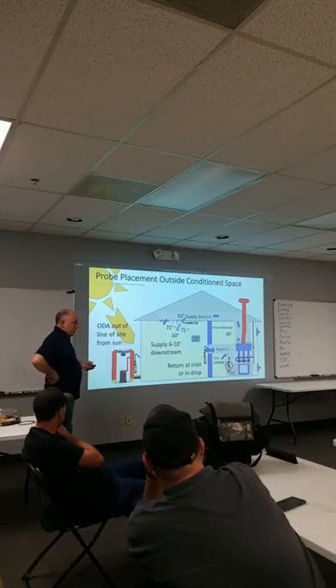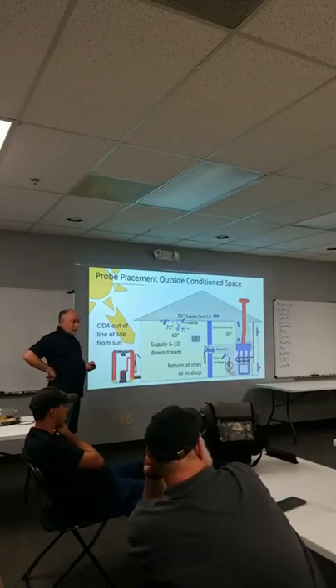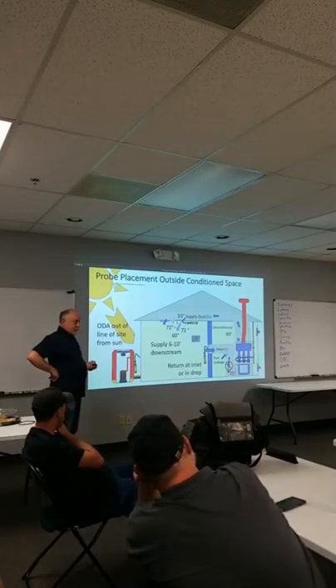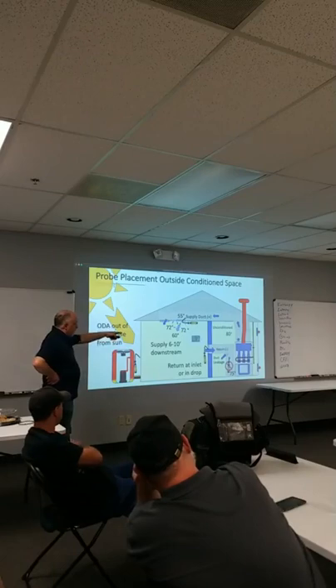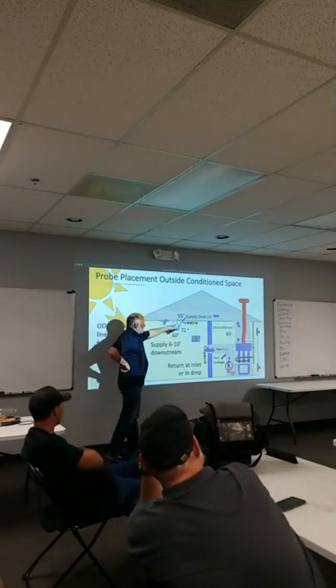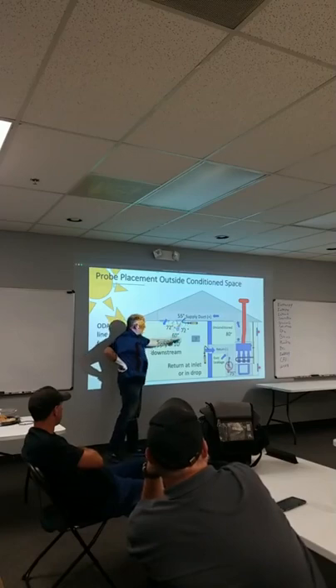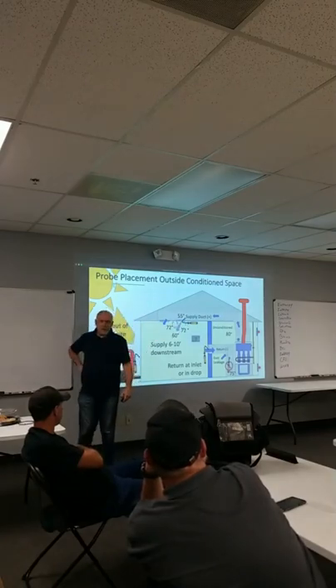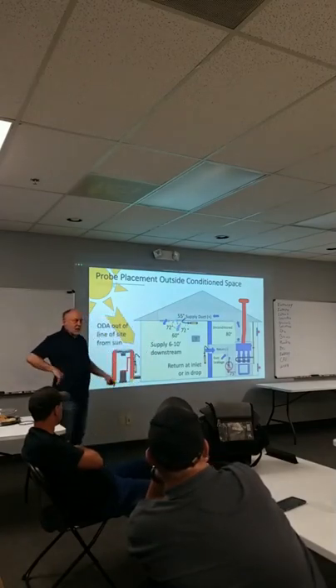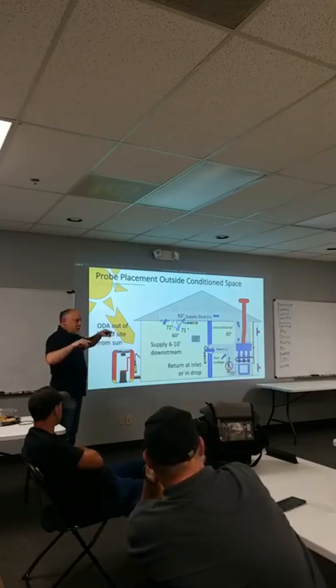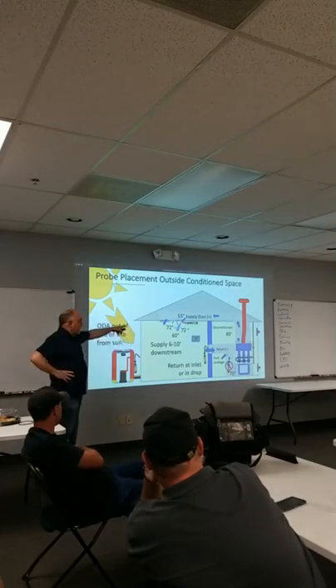Well, in a library, they have the air ducts under the floor, so you have all these orifices. Yep, orifices. Yeah. So when we're doing this type of testing, we wanna make sure that we're in the supply duct. As the air comes out, even an inch away from the register, you're gonna start to entrain air, because you're gonna get a mixed air temperature. As soon as the air enters the room, it's called the Bernoulli effect, the high velocity air is gonna entrain air behind it, and you're gonna get a mixed air temperature.